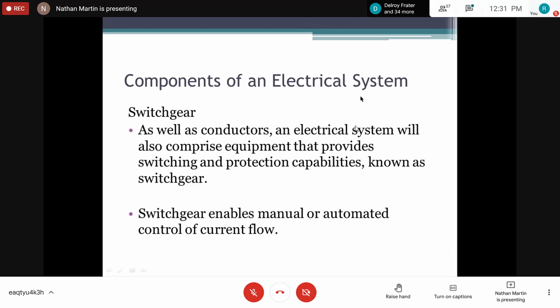So those are really different types of switchgear, right? Your bus bar chamber, your single phase panel, your three phase panel, these are all just different types of switchgear that they use. Now, in some industrial application or some commercial operation, these switchgears can be operated remotely, such as when JPS use their automatic reclosers, right? These are set to operate remotely, or they can operate them manually, which is local, right?